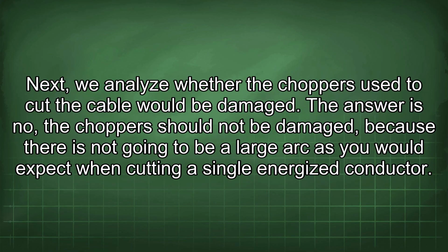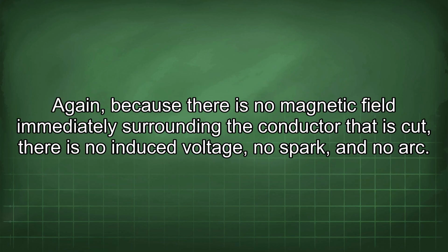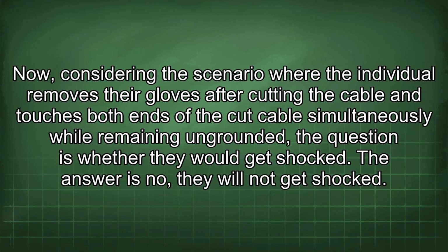Next, we analyze whether the choppers used to cut the cable would be damaged. The answer is no, the chopper should not be damaged, because there is not going to be a large arc as you would expect when cutting a single energized conductor. Again, because there is no magnetic field immediately surrounding the conductor that is cut, there is no induced voltage, no spark, and no arc.